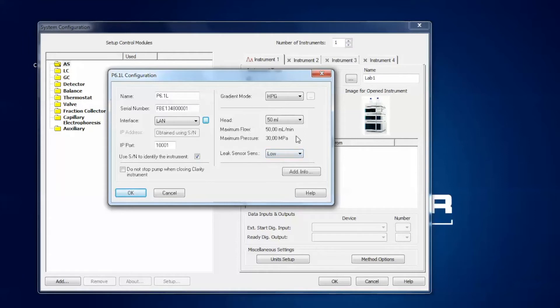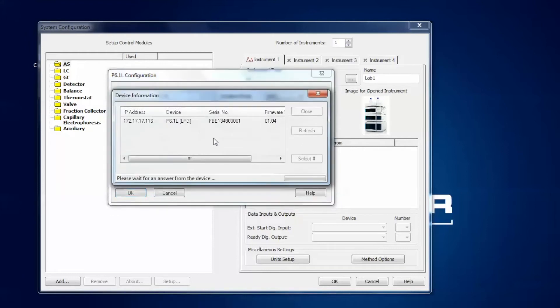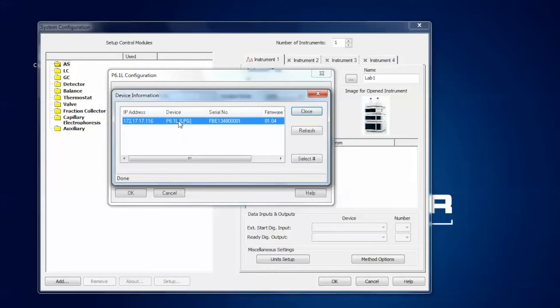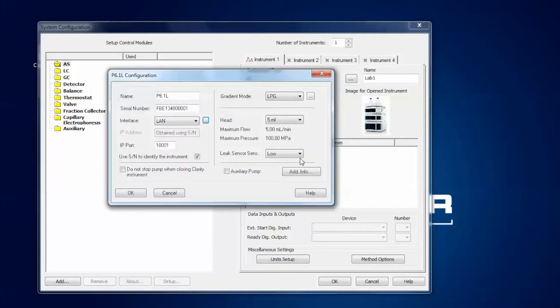I changed a lot of these settings and can't remember the original ones, so I click here again to search the network. We can see it was an LPG pump, and clicking select refreshes the pump head size and gradient mode. In general, we recommend keeping the settings as taken by the software to avoid any problems. You can also select the option to not stop the pump when closing the Clarity instrument — if you want this option just tick it here. That's the configuration of the pump, so click OK to confirm.